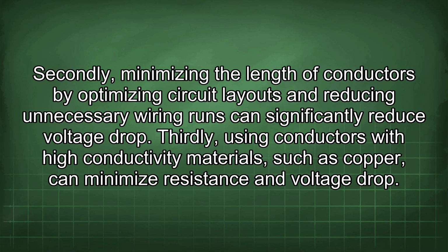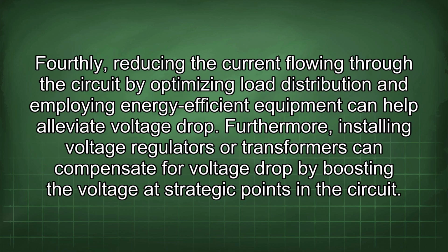Secondly, minimizing the length of conductors by optimizing circuit layouts and reducing unnecessary wiring runs can significantly reduce voltage drop. Thirdly, using conductors with high conductivity materials, such as copper, can minimize resistance and voltage drop. Fourthly, reducing the current flowing through the circuit by optimizing load distribution and employing energy-efficient equipment can help alleviate voltage drop.